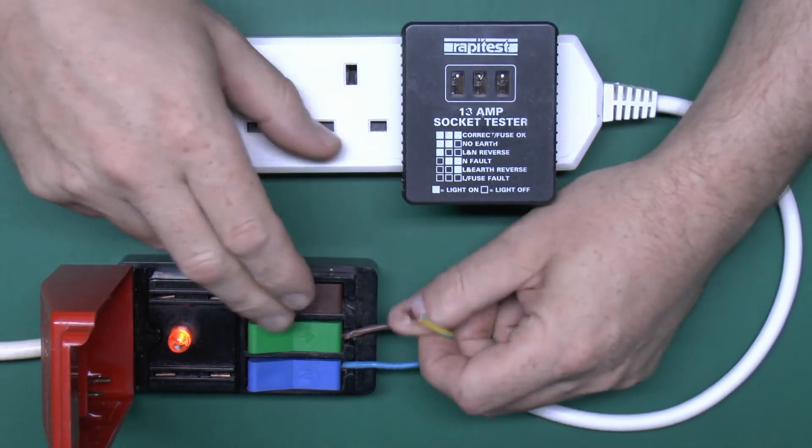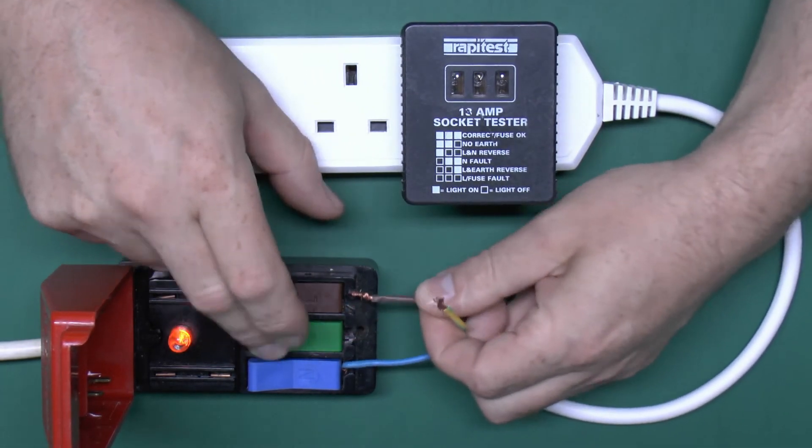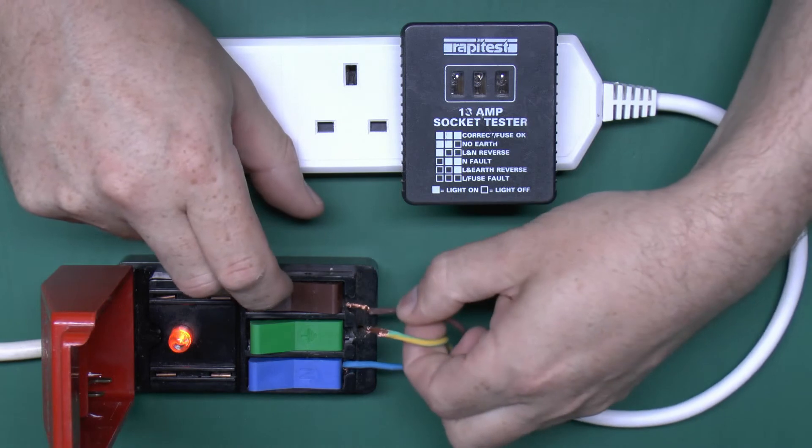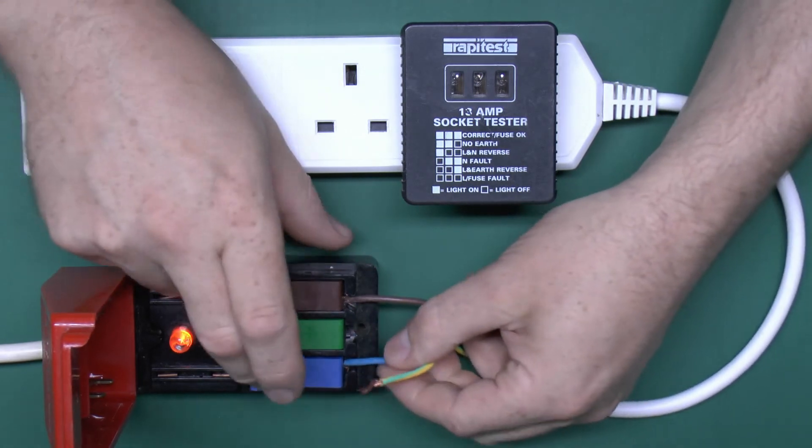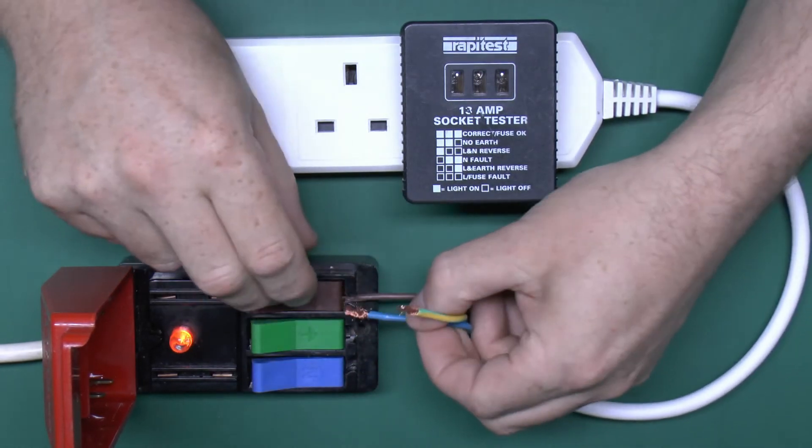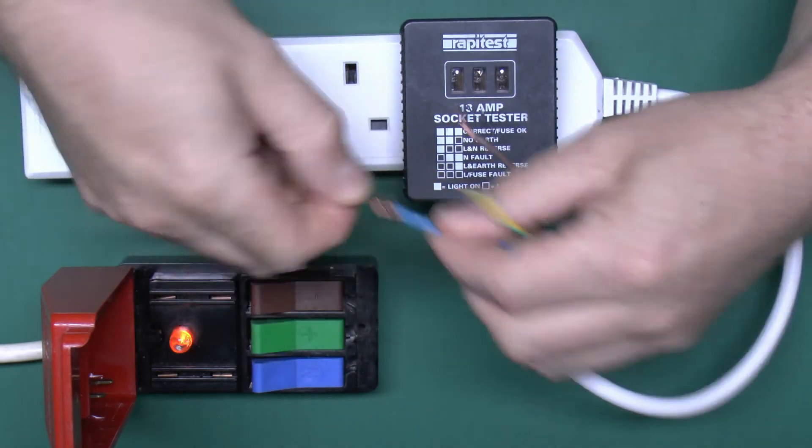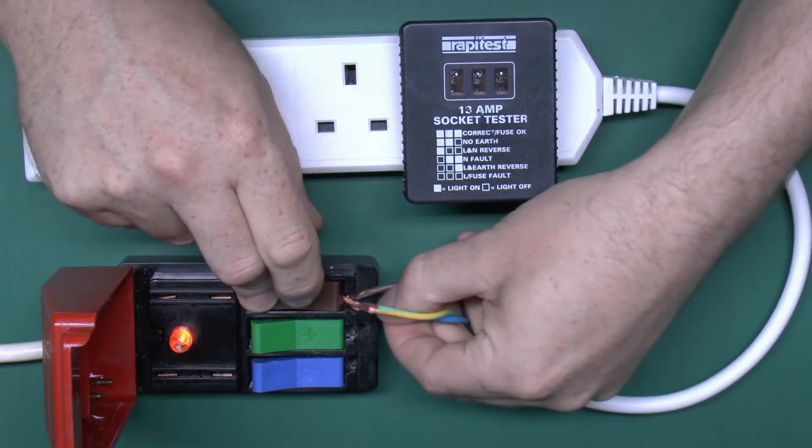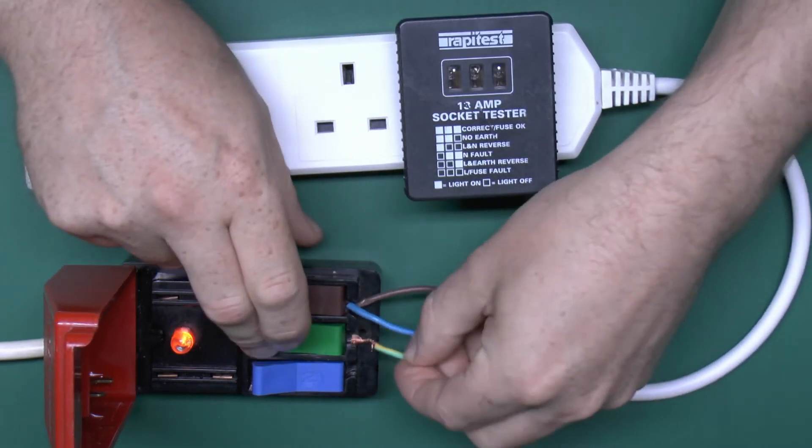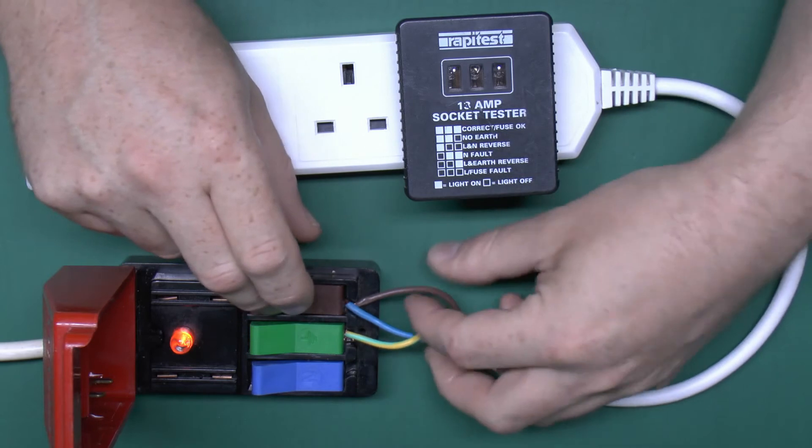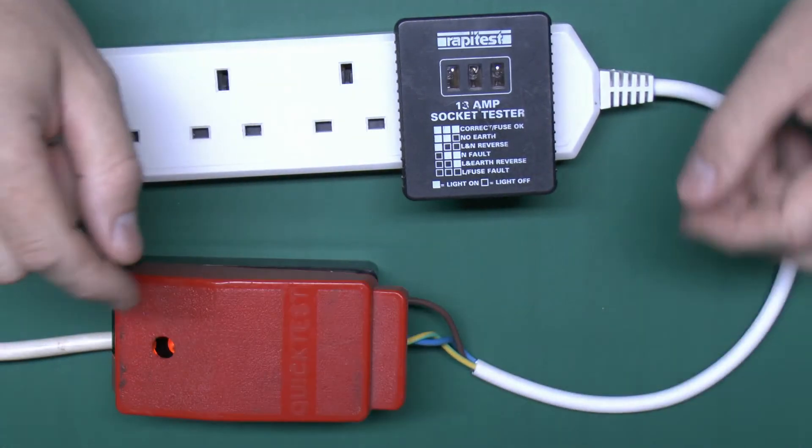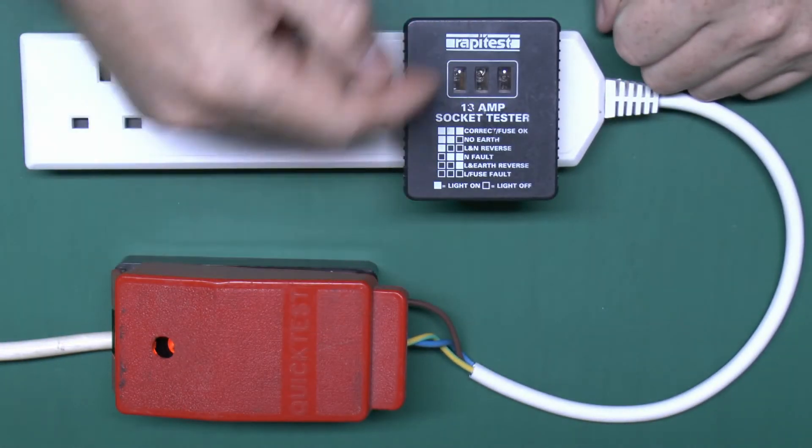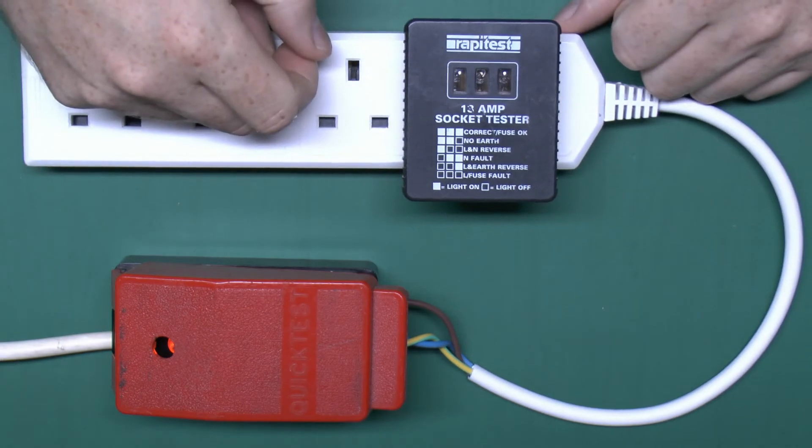So here's some examples of other possible mistakes here. So for example, if you have two connected to the same, how about line and neutral connected to the same terminal. Let's tighten that up a bit, so we have two in there, and we'll assume the earth was connected just like that. And what do we get? Well, who knows, because none of these are actually going to be applicable.